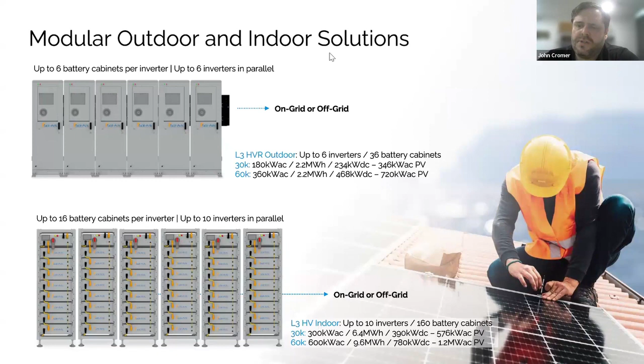When you go indoors, if you build a room, you put in your air handling equipment, we allow you to do a much larger system, up to 10 inverters in parallel, up to 16 battery cabinets per inverter. Now you will have to provide your own busing system at that point, but you can do gigantic battery systems that would be capable of backing up convention centers in terms of their storage capacity. So, much larger if you want to use our indoor series.